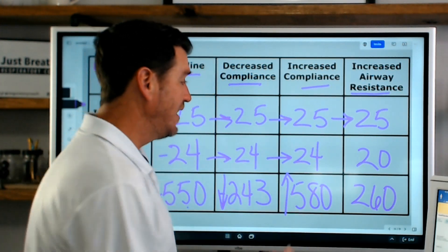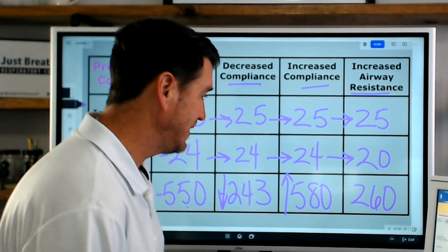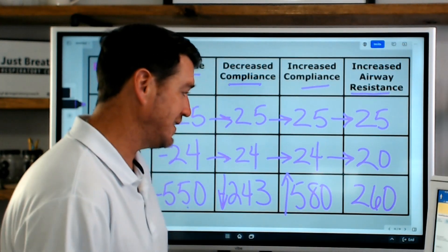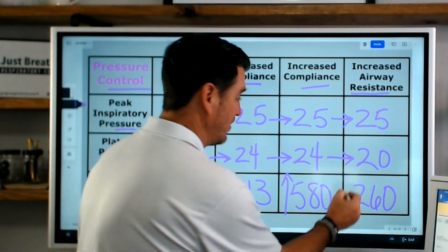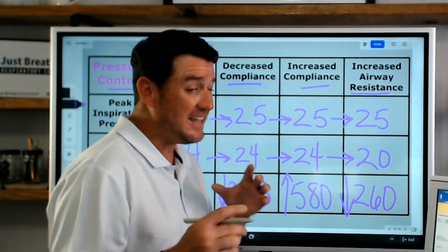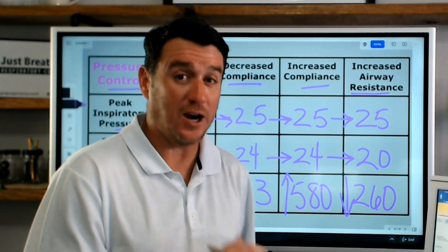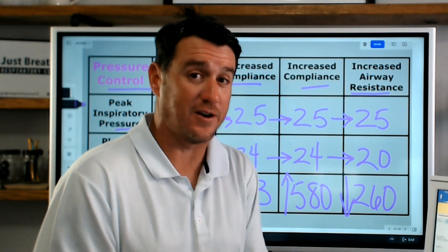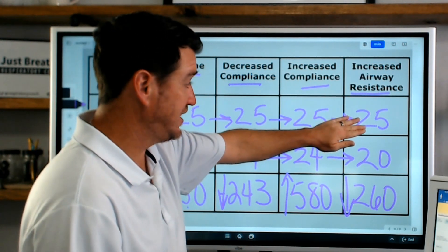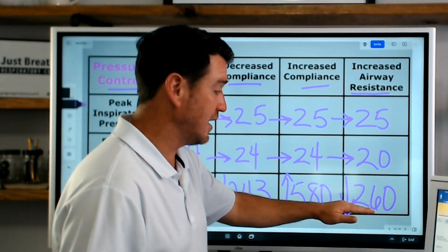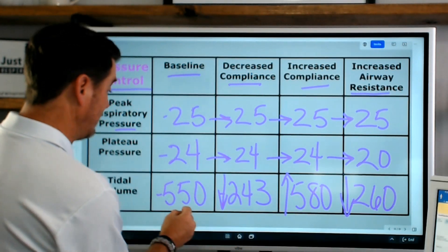We increased the airway resistance. Our peak inspiratory pressure stayed at 25. We did get a little dip in our plateau pressure, which was kind of odd - I'll be diving into that to figure out why, because I wasn't expecting that to happen. But look at our tidal volume - way down. We're seeing that airway resistance has a big effect on the variable. In pressure control, the pressure is set, but it had a major impact on our volumes delivered - we got a small tidal volume compared to baseline where we were getting 550, basically cut in half.